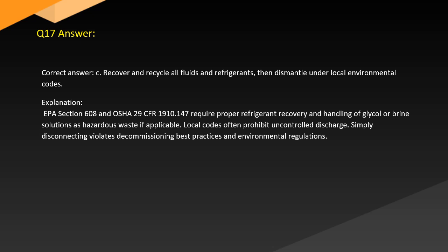Answer. Correct answer. C. Recover and recycle all fluids and refrigerants, then dismantle under local environmental codes. Explanation. EPA Section 608 and OSHA 29 CFR 1910.147 require proper refrigerant recovery and handling of glycol or brine solutions as hazardous waste if applicable. Local codes often prohibit uncontrolled discharge. Simply disconnecting violates decommissioning practices and environmental regulations.